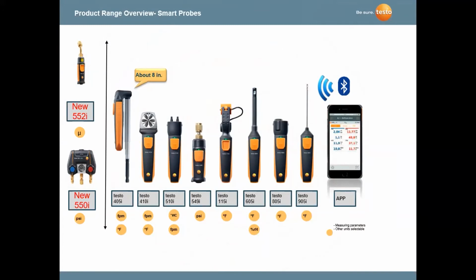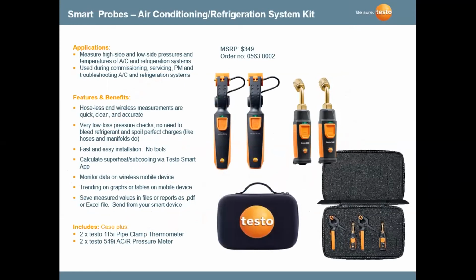You can see we start at airflow, with differential manometer, pressure, pipe clamp probes, and relative humidity. Some of these you've seen in the previous slides. We keep adding to these. These probes start at around $80 and can go up to $120 individually. Then you start looking at kits. This is a superheat subcooling kit where you've got 2 pressure probes, one on the suction and one on the liquid, and 2 pipe clamp probes, one on the liquid line and one on the suction line. We calculate superheat and subcooling through the app itself, so there's no remote display other than your smart device.